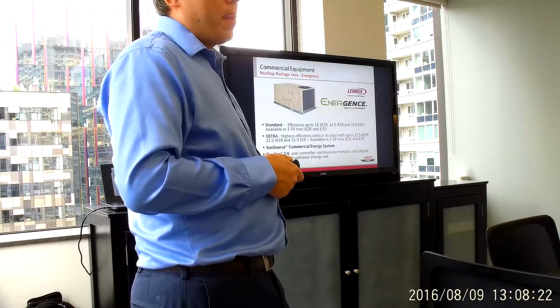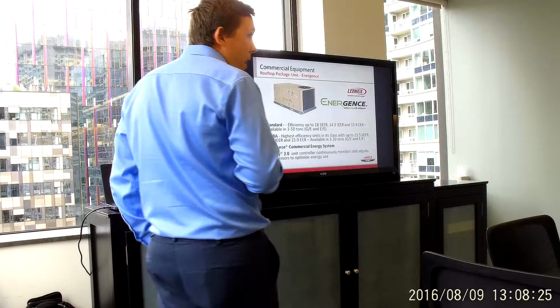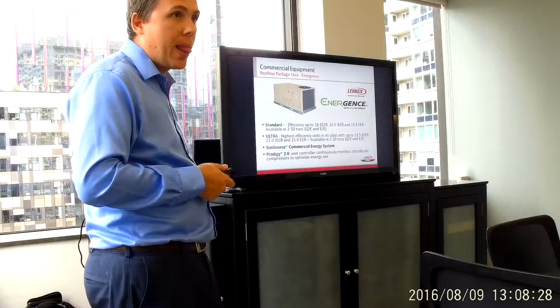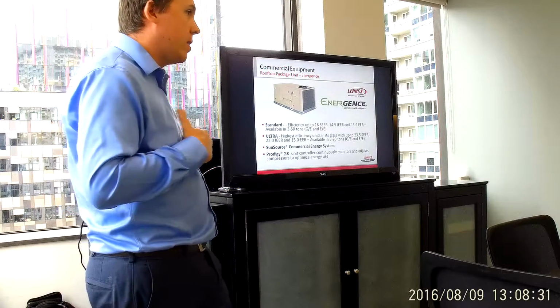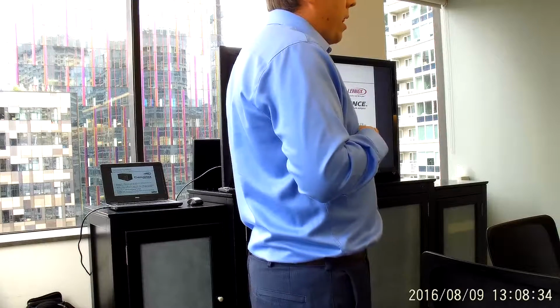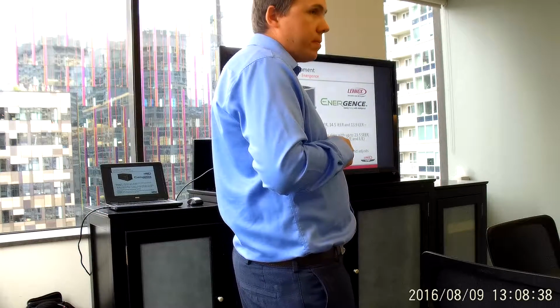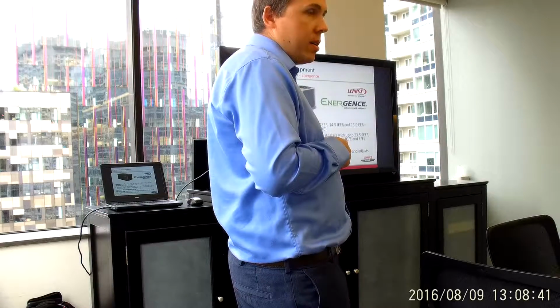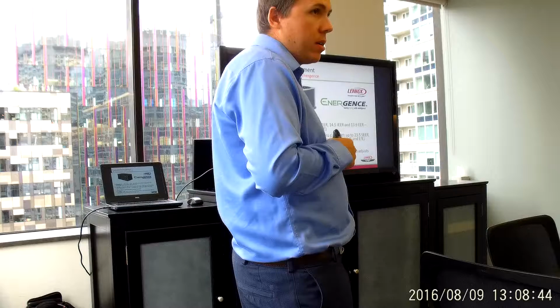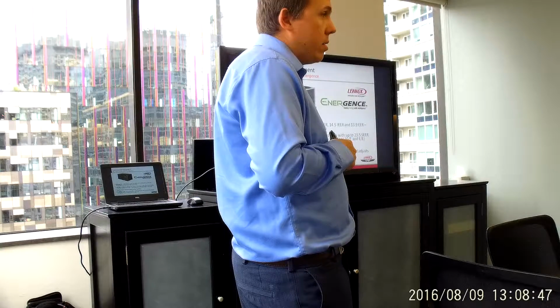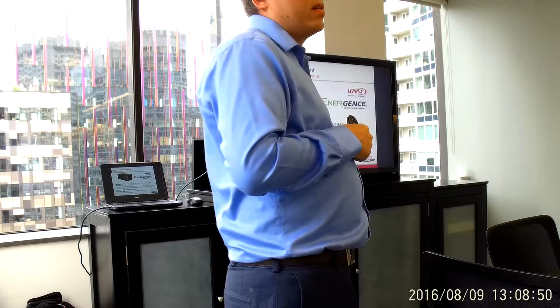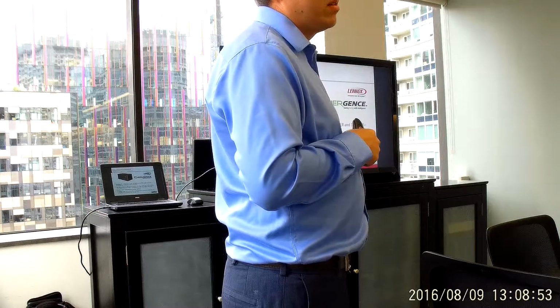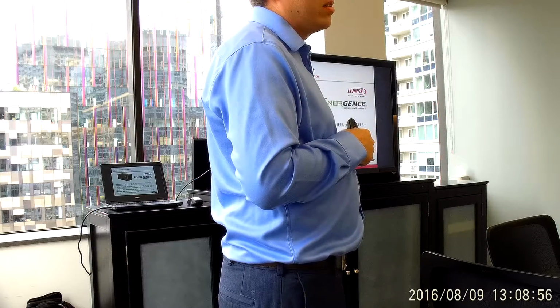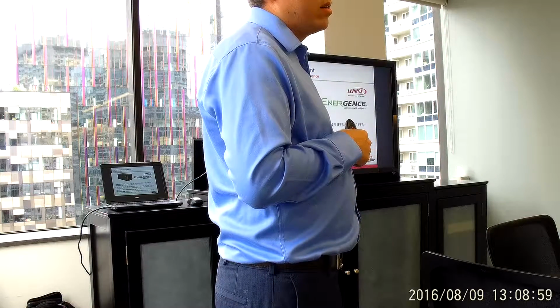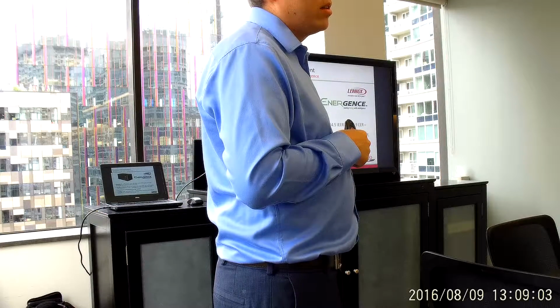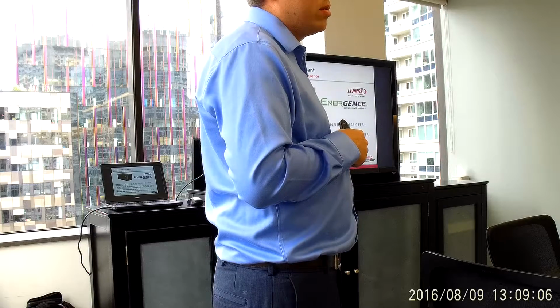All the Energence meet the new code. Do they meet the economizer exception? They do. Not on a package unit, you can't do it on a package. But if you're doing a decoupled ventilation heat-cool system, you can still add an economizer, and that economizer does meet the requirements of the new energy code as well. So it's a choice - say you had a 5-ton unit at around $6,000, does the owner want to spend an additional $1,000 for an economizer? That's still separate from the ventilation system, just free cooling at that point. But it does meet all the leakage, fault detection, all that fun stuff.